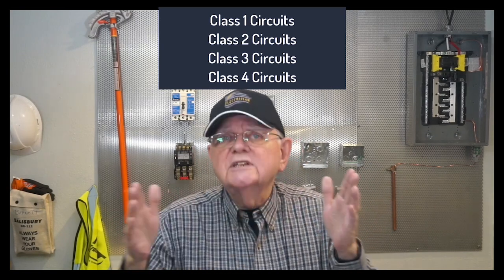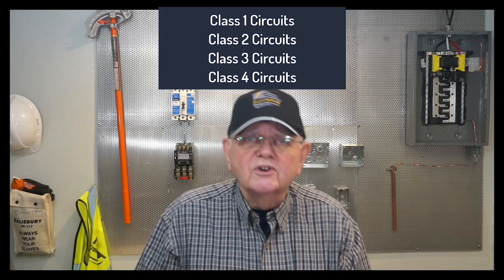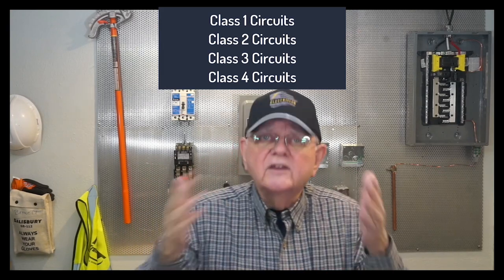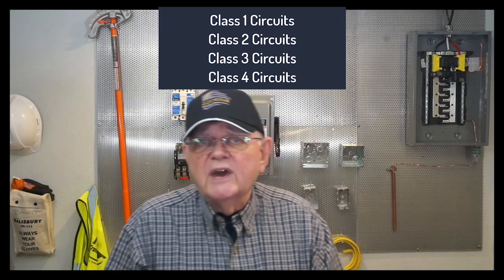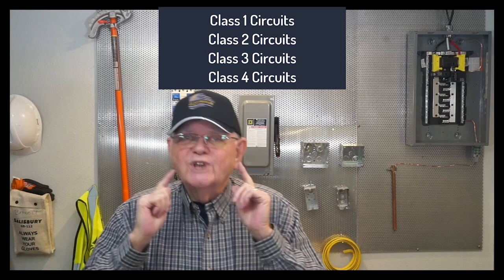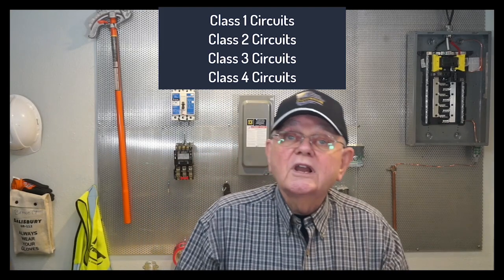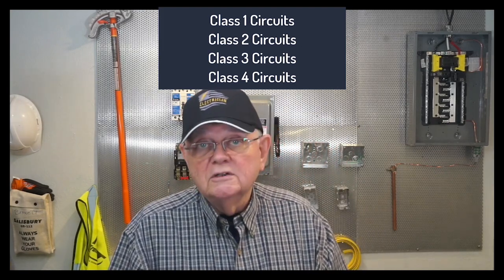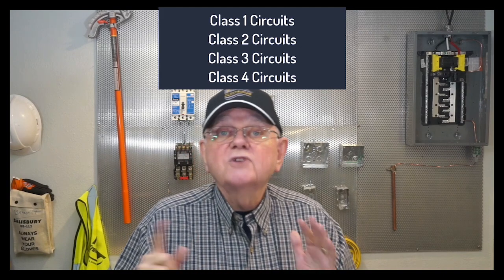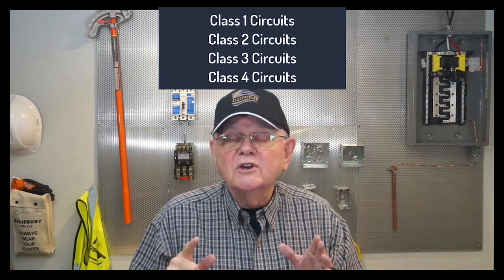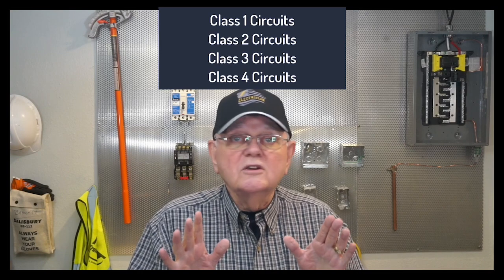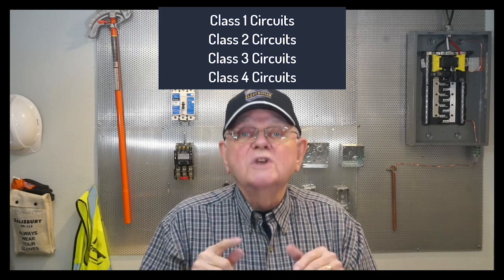So those circuit conductors become the class 2 circuit conductors and so forth. And then the same is true with class 3 power supplies. For the 2023 code, as you're probably aware, there's a new definition for class 4 power circuits. And these are also called fault managed power circuits. And it only applies to Article 726, which is on fault managed power systems.